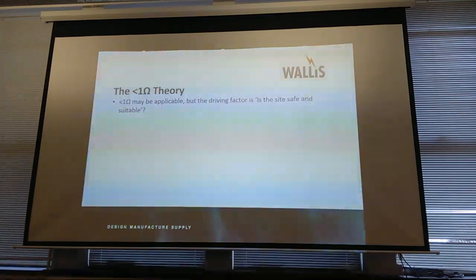Not what the resistance value is, because it's all going to be down to your fault currents coming into the site. It's going to be down to the resistivity of the ground. It's going to be down to the clearance times. So whether 1 ohm is right, wrong, or indifferent, it's one of those. I mean, we can go to a site, and if it's got a high fault level with a slow clearance time, we might need to get the earth electrode system down to 0.1 of an ohm. If it's the other way, and you've got quite a low fault level, then you can get away with 5 ohms or 6 ohms, depending on what the configuration of the network is. So it's not as easy as just saying, put a less than 1 ohm earth rod in, you're good to go, everybody's safe.